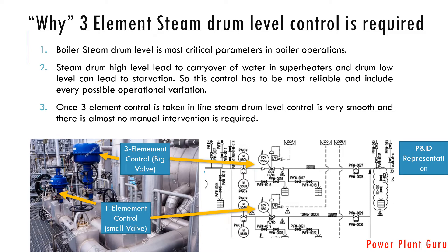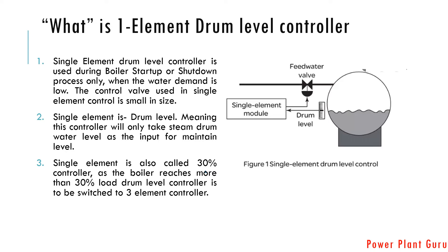To maintain boiler drum level thoroughly, we need three-element level control. First of all, the conventional steam drum level system uses only single-element level control, and that single element is drum level.